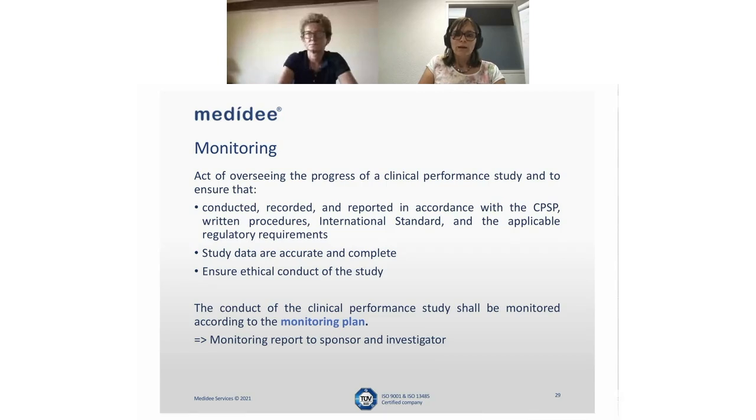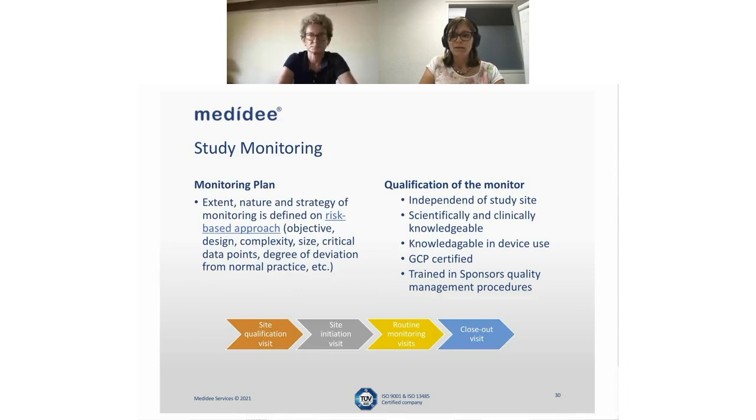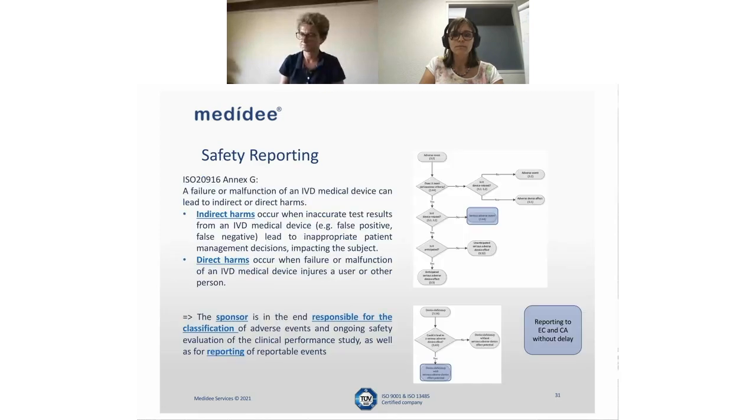You already need to as well really think about the monitoring activity, because the study needs to be monitored according to a plan, and this monitoring needs to be done by someone who is trained, who has knowledge in the field and is GCP certified. The monitoring activity will take place throughout the clinical performance study at several time points, and you have to do this based on a monitoring plan which is designed through a risk-based approach.